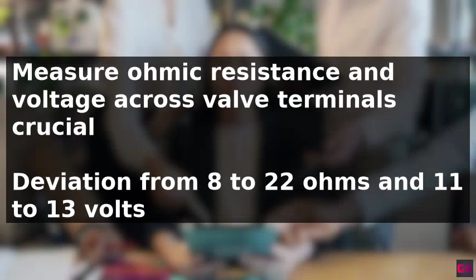The gas solenoid wiring harness should also be checked for loose or damaged terminals, with any faulty components repaired or replaced as needed. Measuring the ohmic resistance and voltage across the valve's terminals is crucial. If the resistance and voltage deviate from 8 to 22 ohms and 11 to 13 volts, respectively, the valve and venturi assembly may need to be replaced.